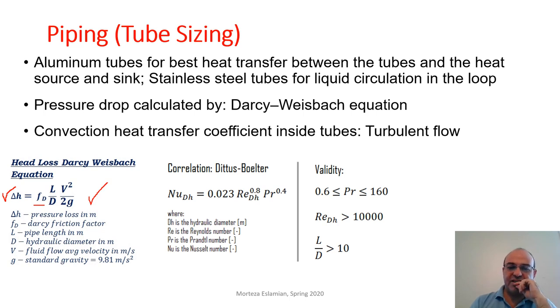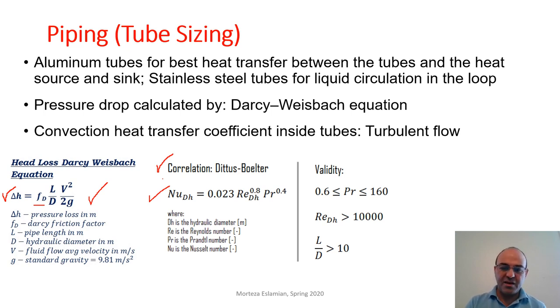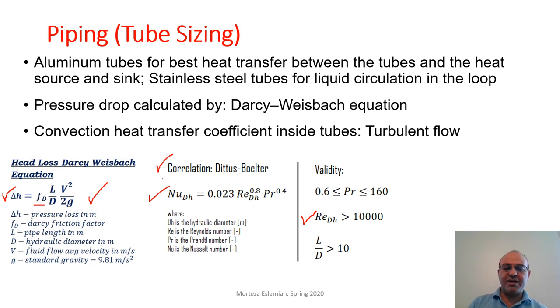This head loss due to major losses, plus the minor losses, equals the total head that must be compensated by the pump. For the turbulent region, which is recommended because the friction factor is minimized and heat transfer increases with Reynolds number, the Dittus-Boelter correlation gives the Nusselt number as a function of Reynolds number and Prandtl number, with a specified range of validity.